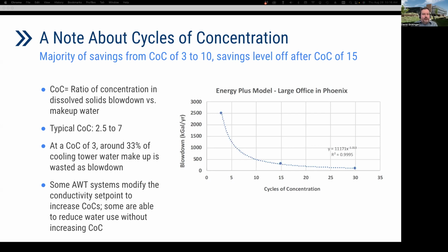Reviewing the different past reports and webinars will give you more insight into some of the approaches taken. But once you start increasing COCs beyond 10, as this graph shows, there's diminishing water savings where blowdown starts to level off. So then there are 2 common ways of measuring COC. The first is the water balance approach, and that is where you take makeup consumption divided by blowdown consumption. And this is the recommended way to measure water savings before and after deployment of AWT systems to properly capture the net effects. The other approach is the COC by measuring conductivity of blowdown divided by makeup conductivity. And what we found, though, is with some of the AWT systems that treat water between the makeup input and the blowdown output stages, this method doesn't necessarily capture the impact of the system.